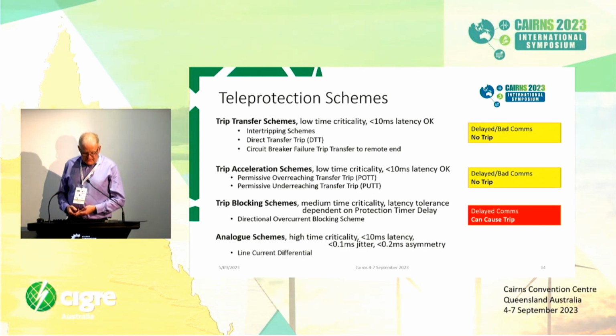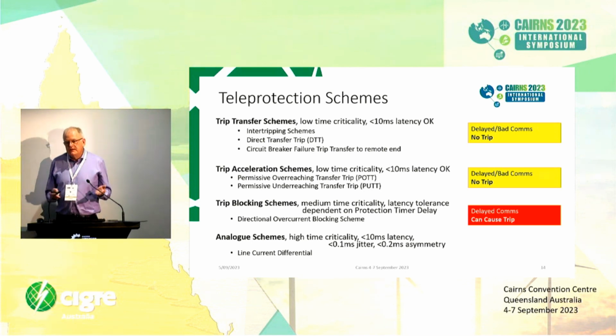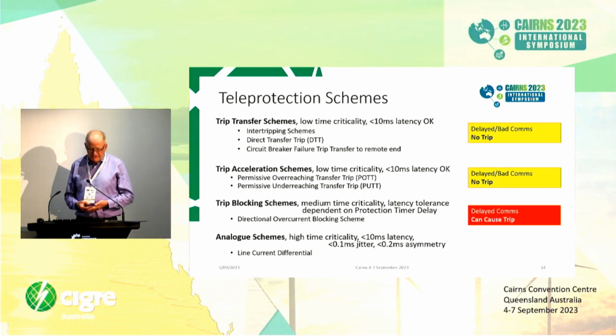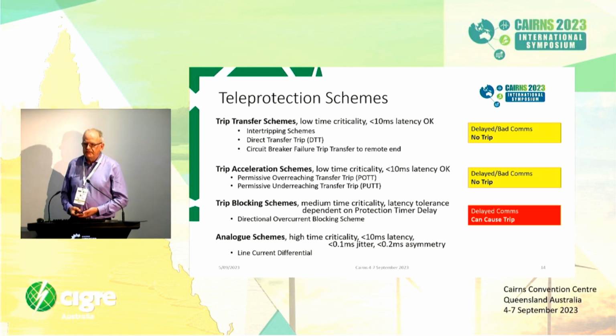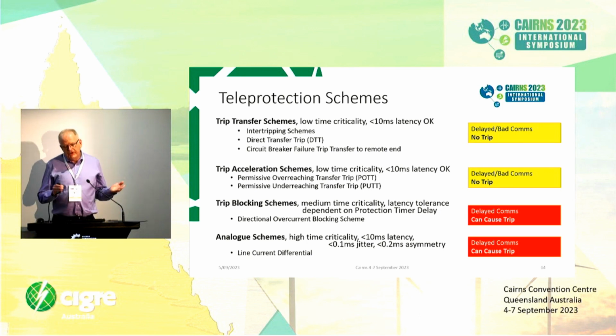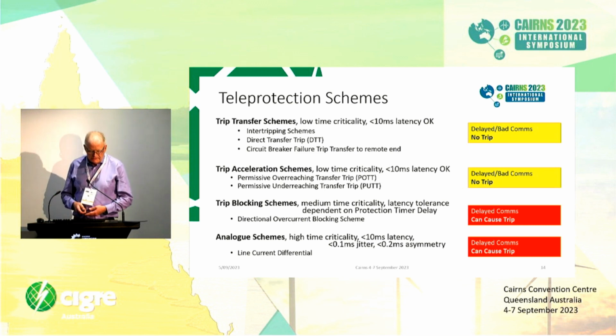And the last type of protection scheme is analog schemes. So this is high time criticality. You certainly still want less than 10 milliseconds of latency. That's okay. What's really critical with these systems is the actual range of deviation in your communications latency, your jitter and your path symmetry, or you can't tolerate asymmetrical communications between the forward path and the reverse path. And typically that's a line current differential scheme, which is really the focus of what we're talking about today. We will also touch on some trip transfer schemes with the GOOSE scheme that Santosh is going to talk about later. So once again, delayed or varied comms can cause the line to trip, so high criticality there.